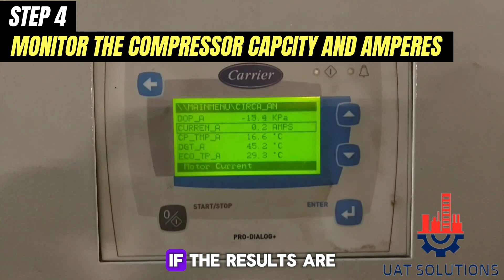After the loader and unloader valves are replaced, install the solenoid coils back and start the chiller. The moment the compressor starts, check the compressor capacity shown in the display and the current consumed by the compressor immediately. If the results are as shown, then the fault has been fixed and now the compressor is operating as per the capacity commanded by the chiller. Continue to monitor the compressor current and percentage.